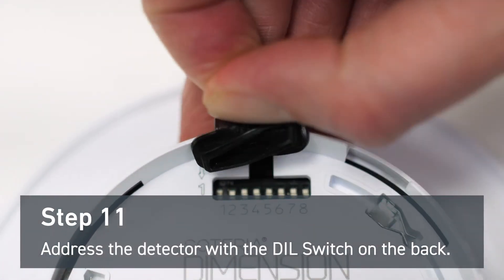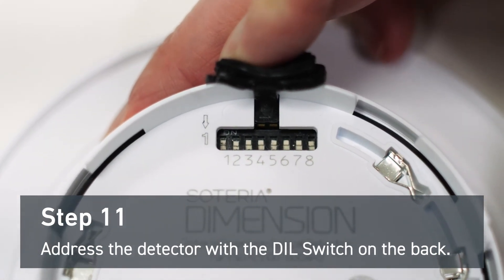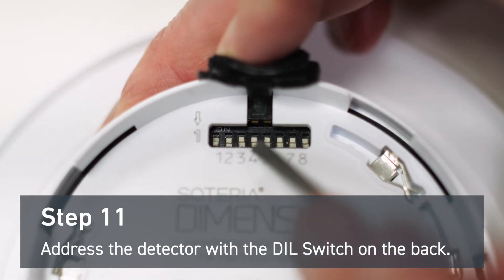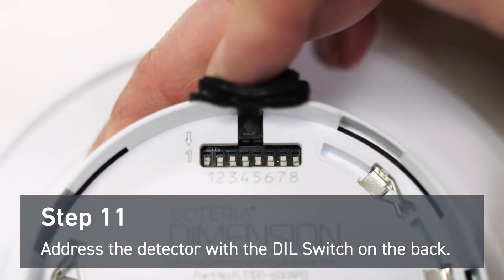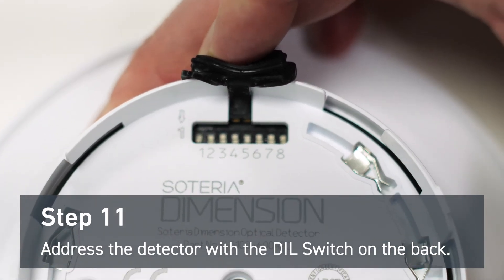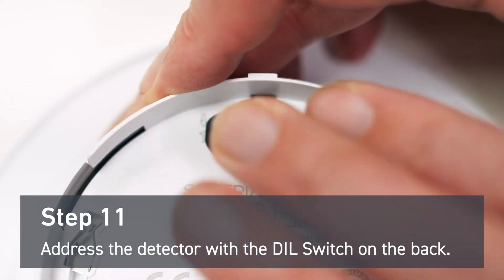Address the detector with the DIL switch on the back. For this demonstration, we're going to give this detector address 17. This means you'll have to switch numbers 1 and 5 to the ON position. The 8th digit is reserved for core protocol applications only. Make sure to push the gasket back into place after you've addressed the device.